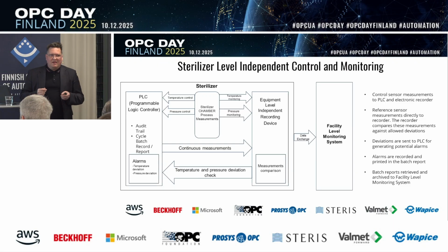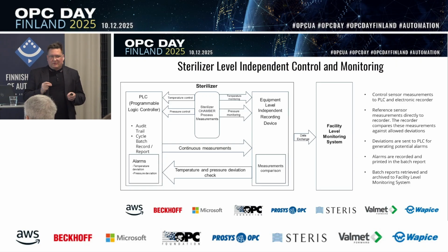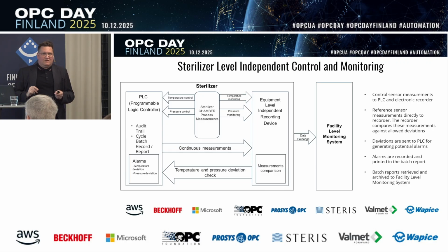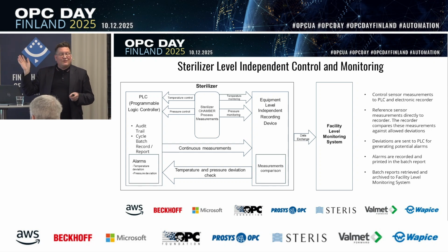The standard way, easily for a sterilizer manufacturer like us, is that you have to equip your equipment with the means to do that. The independent control and monitoring means you have your control temperature sensor and pressure sensor, and then you duplicate those, taking the other sensor next to the controlling one to an independent device. That could be an independent, segregated PLC, an independent electronic recording device, or you can take your data directly out to a central system, cloud, or somewhere else.